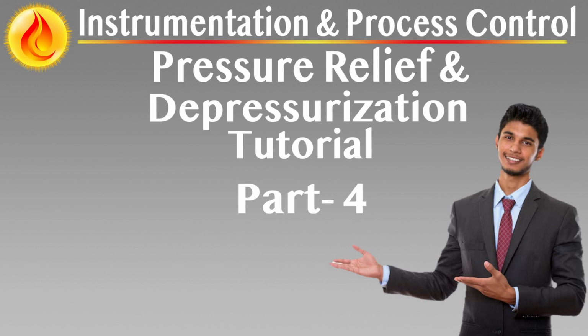Maintainability and access. Devices should be maintainable or replaceable without shutting down the flare system, especially in continuously operating facilities. Include monitoring capability in the control room or distributed control system, DCS, for real-time operator feedback. By incorporating accurate and reliable flow measurement in flare and vent systems, operators gain critical visibility into process safety behavior, emission performance, and operational health, while maintaining the passive, fail-safe nature of the relief system itself.